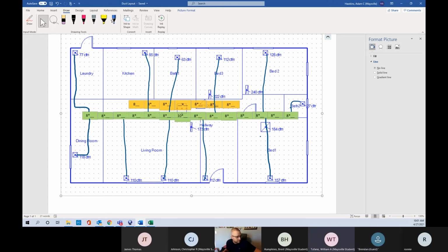So if I'm reading this right, 1,000 CFM at a 0.1 for helix flex duct is a 16-inch diameter round, probably. That's trying to move all of that through one duct, so that would be like a package unit. Most of the time, package units have flex or metal that goes to them, and they have one big takeoff, and then it dumps into a duct system, and that duct system gets pressurized through that flex.